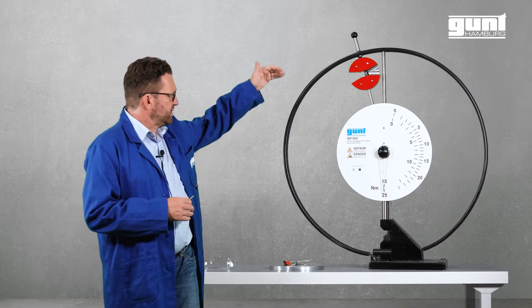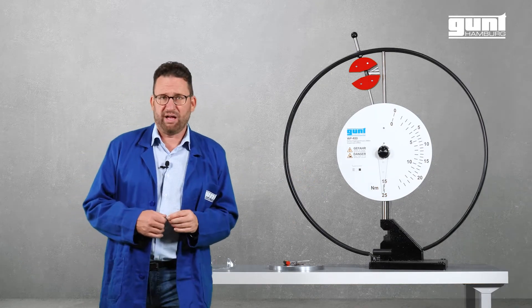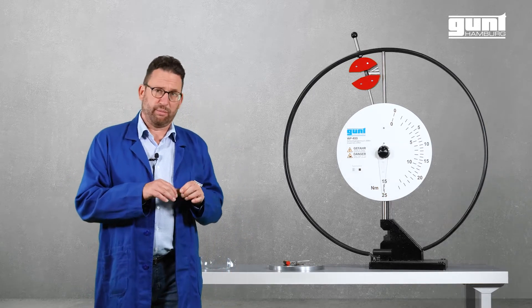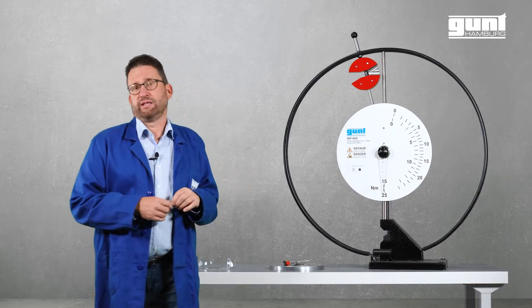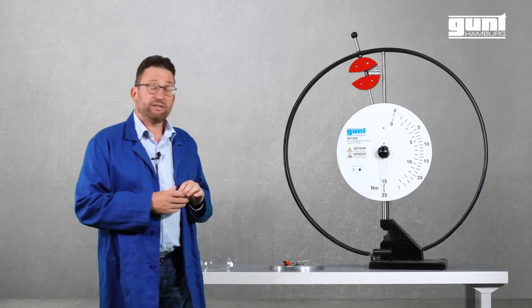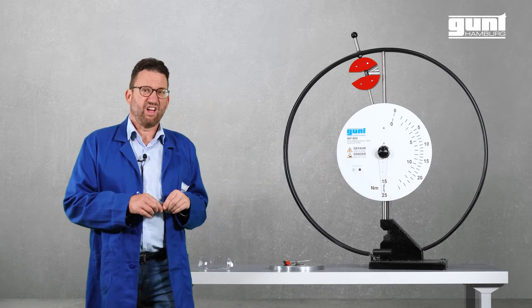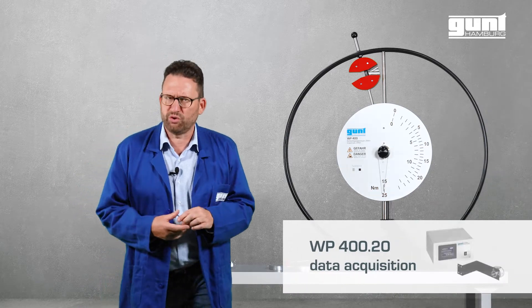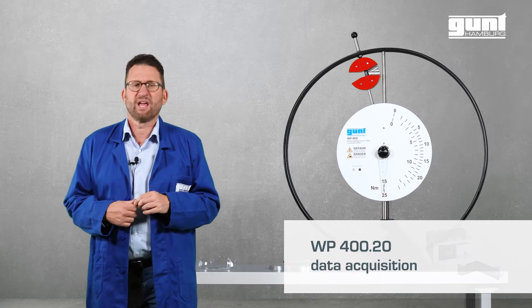In the experiment, the solid pendulum describes an arc at the bottom of which the hammer transfers part of its kinetic energy to the specimen, which is either destroyed or deformed and pushed through the support. The Notched Bar Impact work required to deform the specimen is directly read off the large scale with its trailing pointer, and the data can also be transferred to your PC via the optional GUNT data acquisition software.